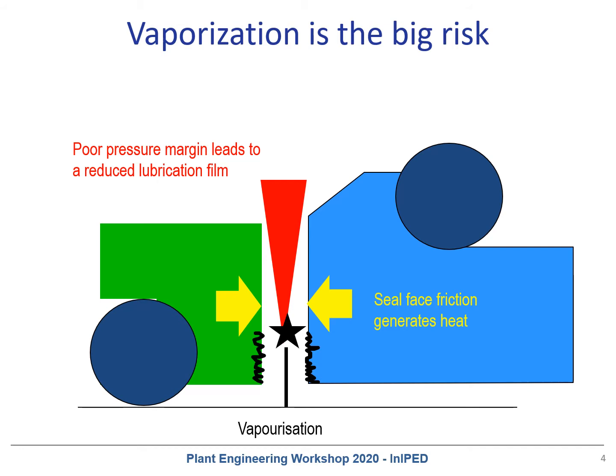Poor vapor pressure margins lead to a reduced lubrication film stiffness. Thus, the point of vaporization is moving, and depending on where it is finally located, it results in liquid lubrication, mixed fluid lubrication, or dry running, which destroys the mechanical seal faces by excessive wear or chipping.